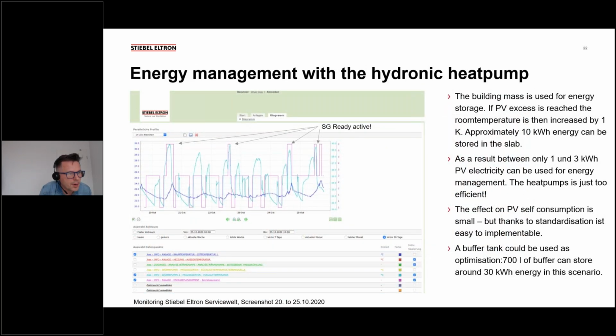Energy management with the hydronic heat pump is possible because it's very easy to do. Software is just activating a checkbox in the controller, and then the heat pump does energy management. So what I do in my case, I measure room temperature, and if the solar PV system says I have excess power, then the room temperature is put up a couple of degrees, like 1 or 2 degrees up. And then the heat pump switches on, it runs with solar energy, PV energy. Typically this works quite nicely in shoulder season, not in typical cold winter. Here you see a week in October where I actually had 5 times the situation where the heat pump was running in energy management.